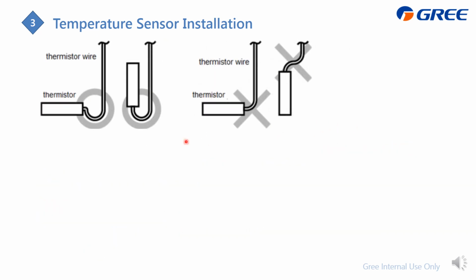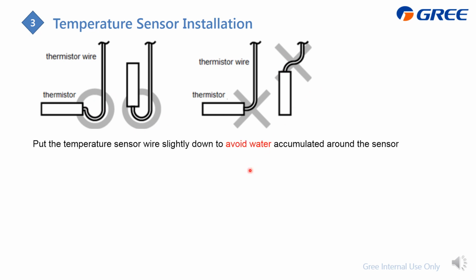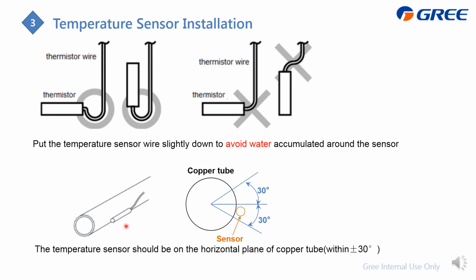When you install the temperature sensor, please avoid to make it like this, which is we require this one to be a U shape, just like this, not directly out. The purpose of it, do you know what is it? Is to avoid the condensing water to accumulate inside the temperature sensor, which will delay or make the detect value not correct. Anyway, it is to avoid the water to get inside. And as for the position, here is the copper pipe. It should be plus minus this 30 degree.